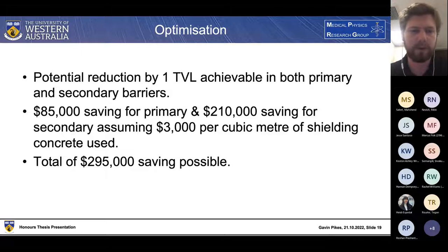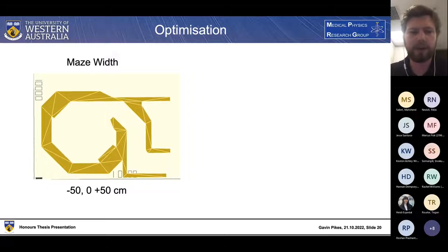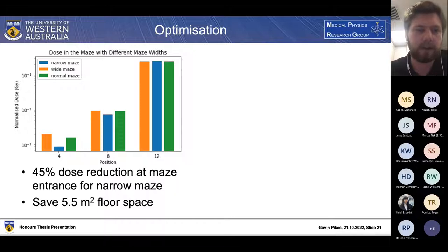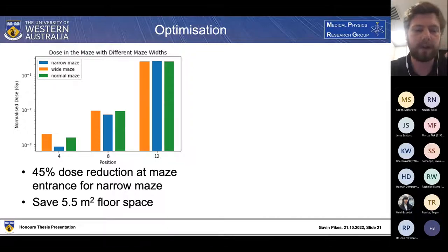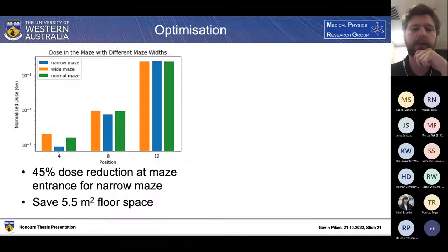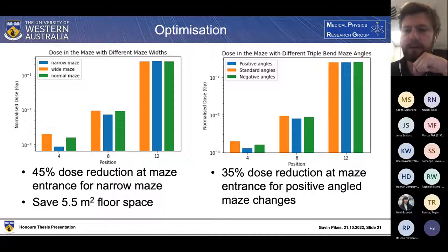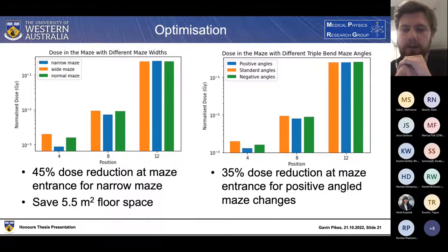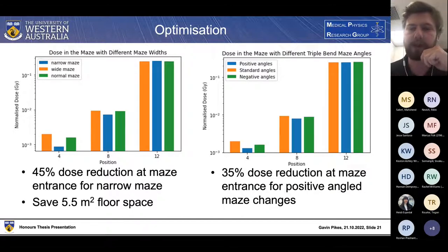We also adjusted the maze width by plus or minus 50 centimetres, and changed the triple bend angles by plus or minus 2, 4, and 6 degrees. Results show a 45% dose reduction at the maze entrance for the narrow maze, with a saving of 5.5 square metres of floor space. For the triple bend maze, both positive and negative angle changes result in a dose reduction at the maze entrance, up to 35% using the positive angled maze changes.